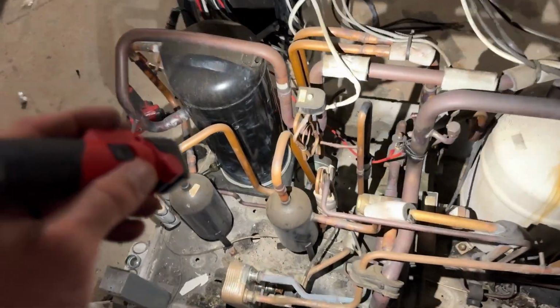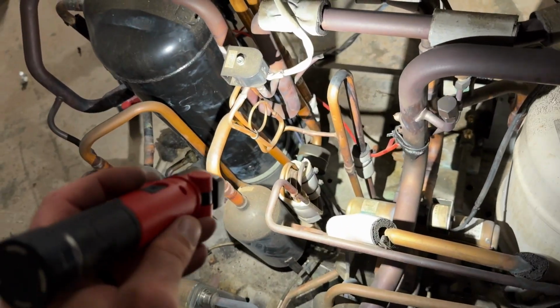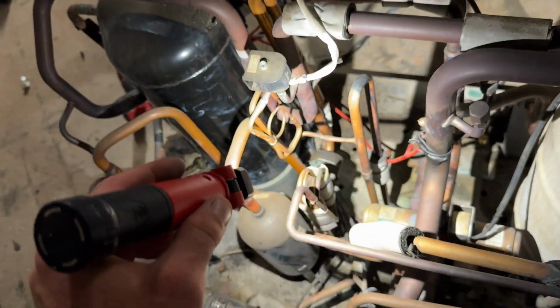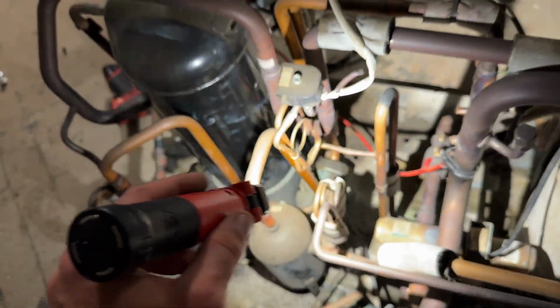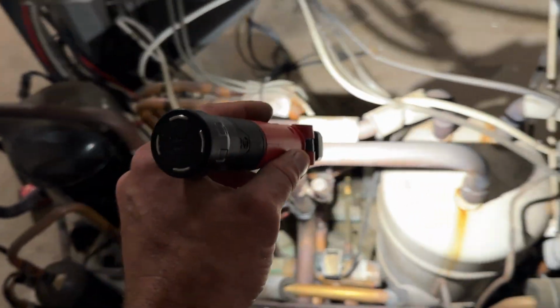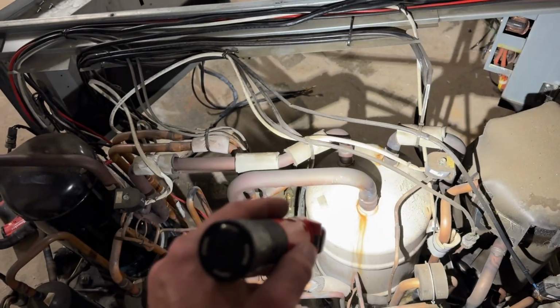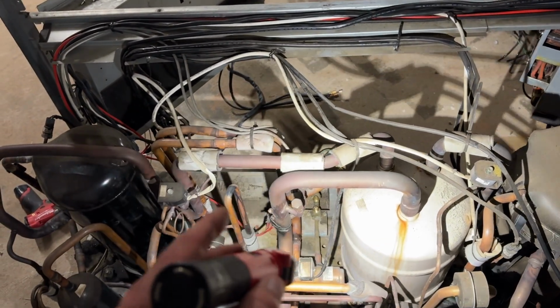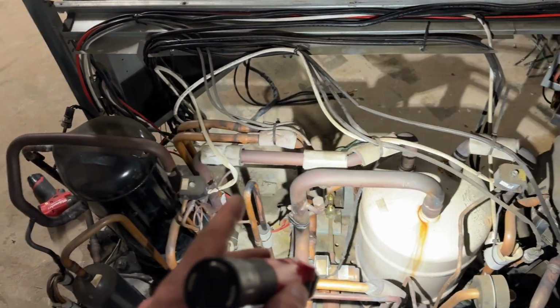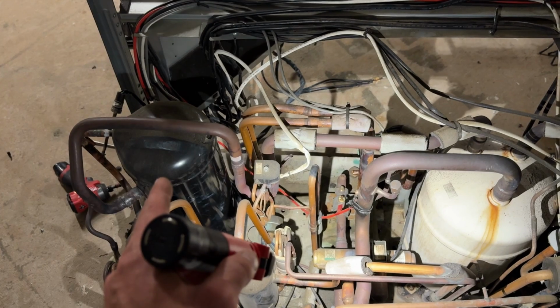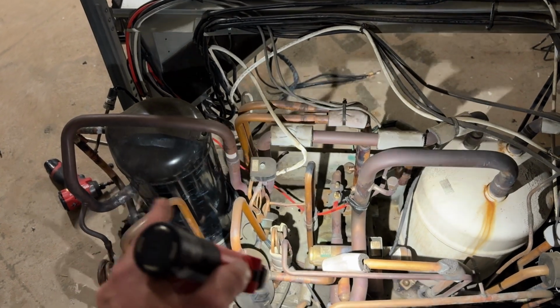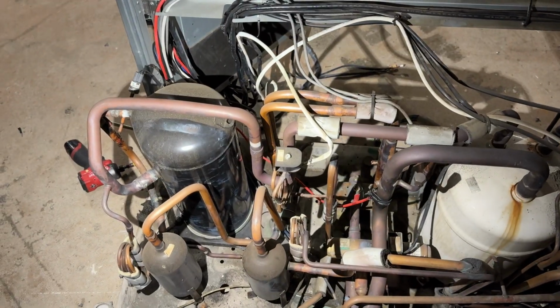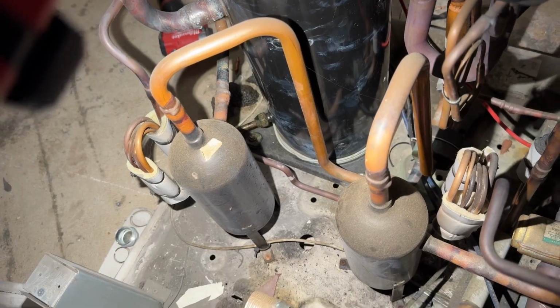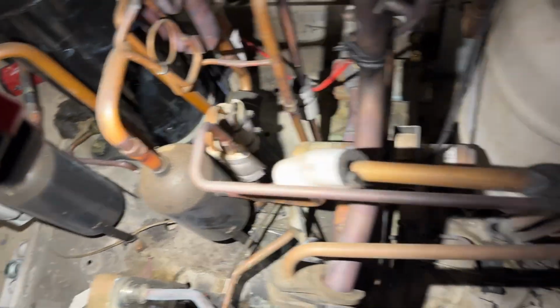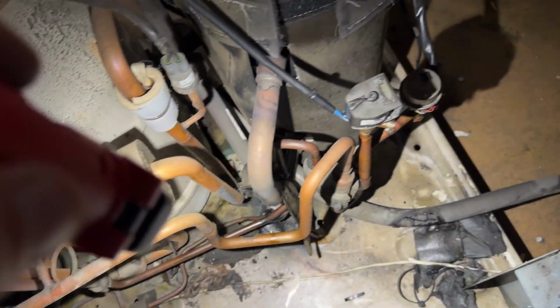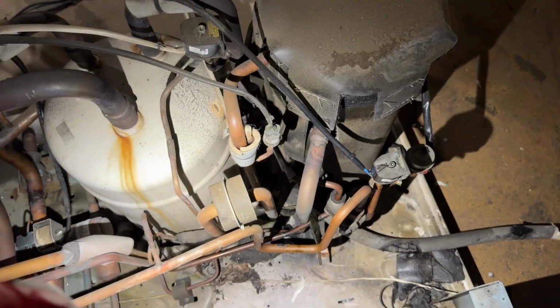Okay, this here is doing the exact same thing. It's also liquid injection. It's just taking a bit of liquid and metering it back, but this time it's going into the receiver. So in this case, that might be if it needs to also cool that down. These compressors are also sharing oil. You can see that there's a line that goes across and connects the sumps.